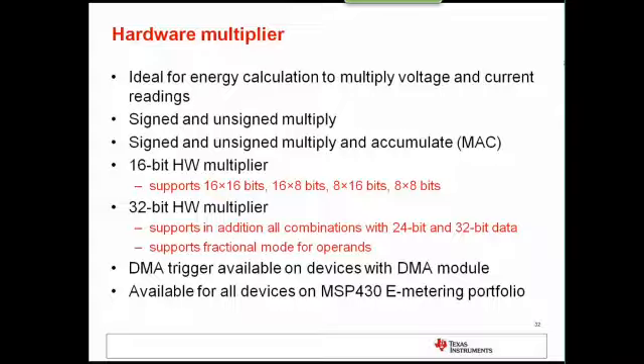There's also a hardware multiplier module on e-meter SoCs, which is ideal for calculation of voltage and current. There's signed and unsigned multiply, and signed and unsigned multiply and accumulate. There are two types: 16-bit hardware multipliers or 32-bit hardware multipliers, and which one is available depends on the actual chip. Also, on some devices, there's a DMA trigger so that whenever you perform multiplications, you can directly send the results to memory.